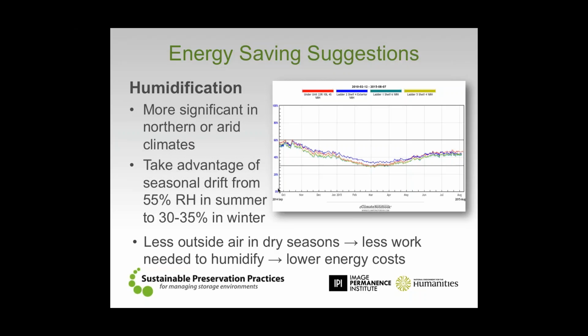Try to make sure that in the wintertime, for most materials, there's really no necessity to humidify all the way to 50% or 55% relative humidity. And if your collection is of the type that you can manage at 30 or 35%, do so. It's going to be a lot easier to control mechanically, and it's also going to reduce the cost of the energy that you're using as you go through.